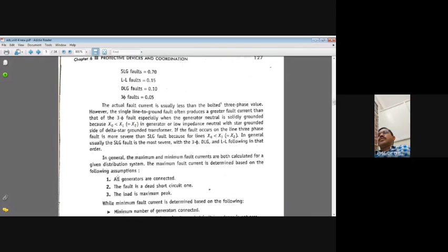In general, the maximum and minimum fault currents are both calculated for the given distribution system. The maximum fault current is determined based on the following assumptions: all generators are connected, the fault is a dead short circuit, and the load is at maximum peak. While the minimum fault current is determined based on the following: a minimum number of generators connected, the fault is not a dead short circuit but the fault impedance is not zero, and the load is minimum.